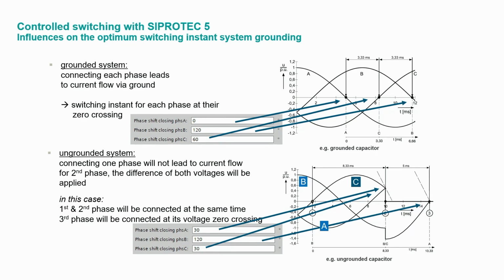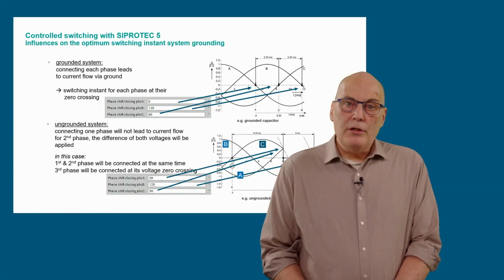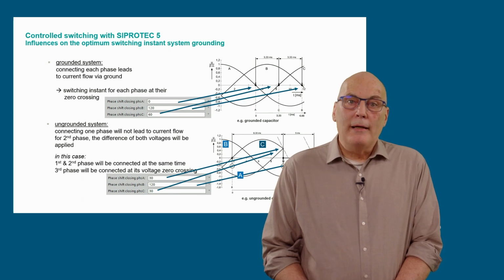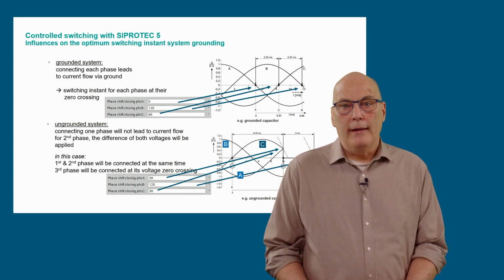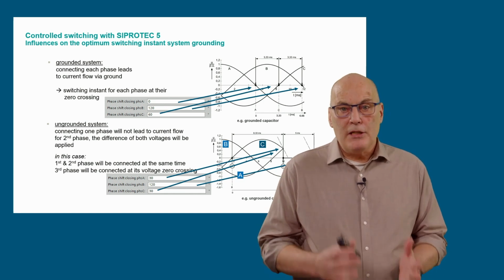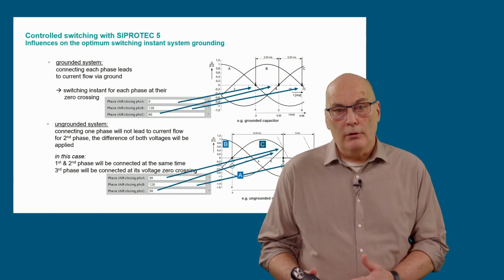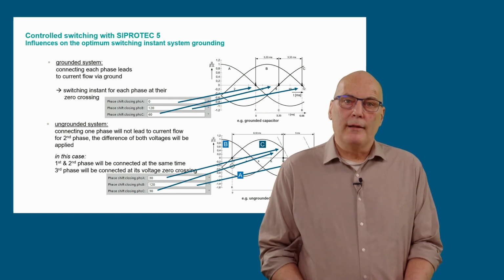If we start at the bottom, we see the closing instance for a capacitor bank with isolated star point, as said on the previous slide. With the first switching in phase A and C at 30 degrees. At 30 degrees on phase A voltage, the A and C voltage intersects so that the voltage VCA has a 0 crossing. Closing poles A and C here will be ideal as the star point is not grounded and there is no delta between the load side. Discharge capacitor equals 0 volts and the in-feed also 0 volt at this point in time.